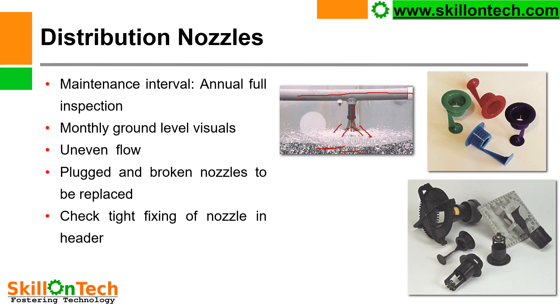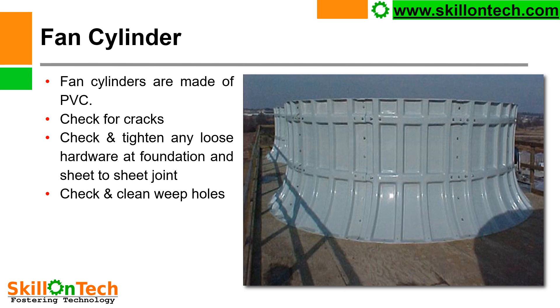These nozzles are also to be checked for tightness in the distribution header. Here in this picture you can see the fan cylinder and fan deck area. These fan cylinders are made of PVC and shall be checked for any visible cracks all over the cylinder. If any cracks are found, that portion shall be replaced with a new fan cylinder segment. The fan cylinder segments are tightened with bolts, and all hardware shall be checked for any looseness. Weep holes that are plugged shall be cleaned, and the fan cylinder shall be intact with the fan deck.